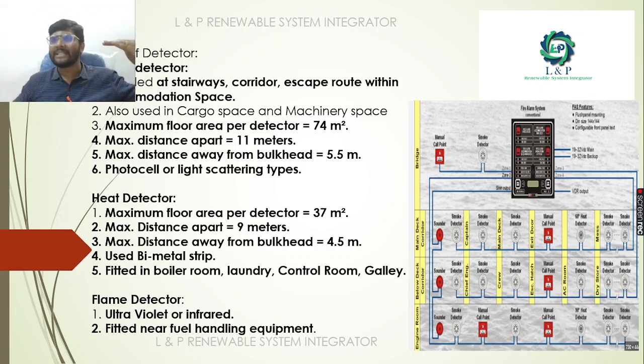The maximum floor area that can be covered by a smoke detector is 74 m², and the maximum distance between smoke detectors can be 11 meters. If you are going for heat detectors, the maximum floor area per detector is 37 m², and the maximum distance between heat detectors can be 9 meters. The heat detector works using a bimetallic strip.